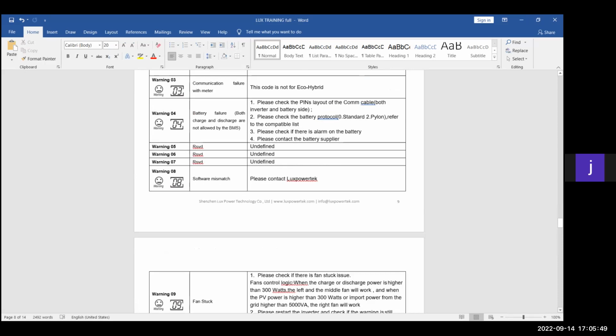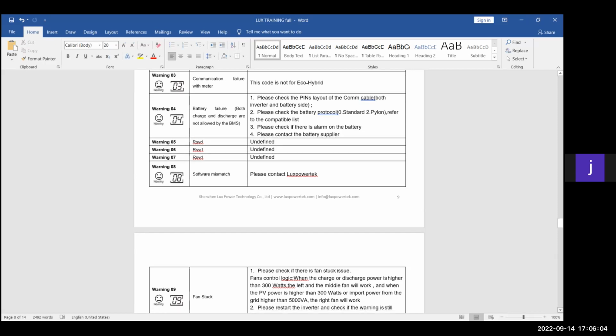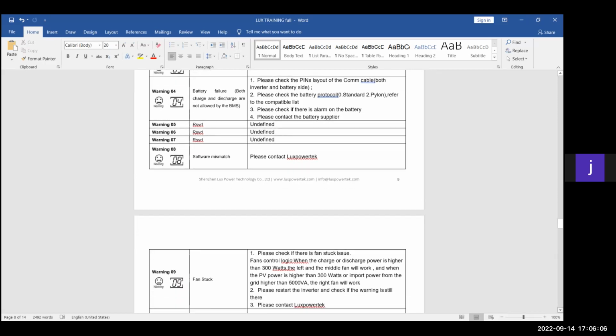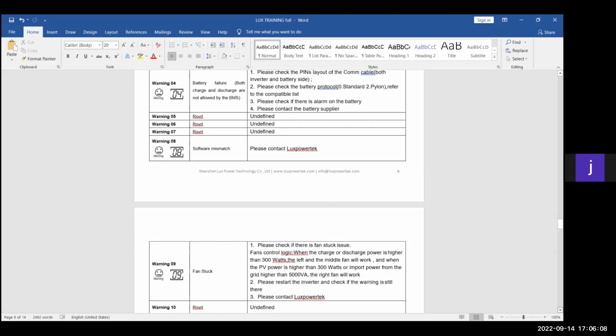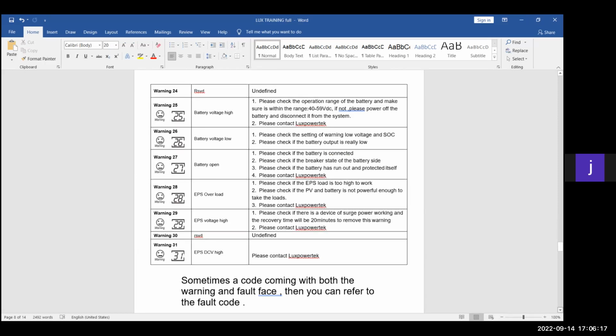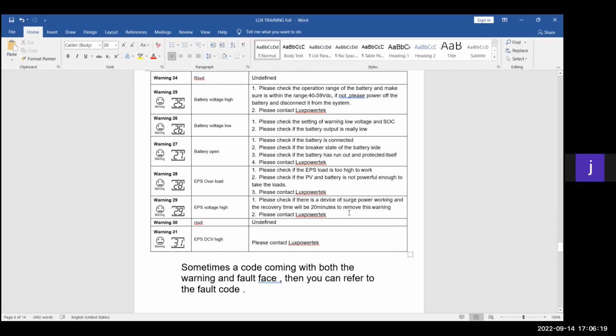and update your inverters. Something that I didn't mention at the top, updates. If it's a parallel system, always update your inverters to the newest software available, to ensure that they are on the same firmware, and that's the only way that you can do it, by updating it completely. From here on, there's not much of the warnings that you'll really get to deal with, so you can have a look. Then the other one that you'll get a lot is your 26.